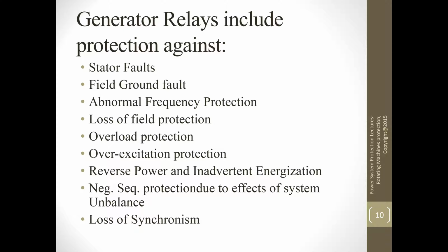Negative sequence protection due to effects of system unbalance. This is also important for us. And loss of synchronism during faults, it might speed up and then we lose synchronism. That is also detected by the protection function.